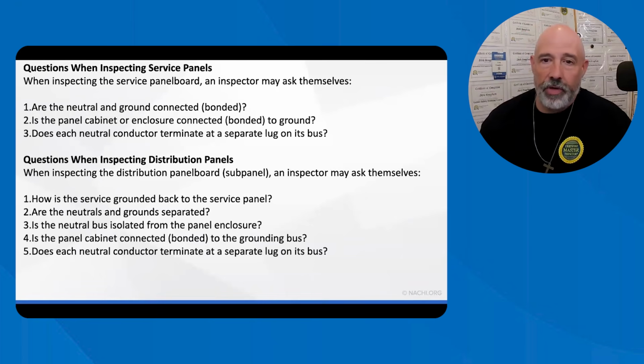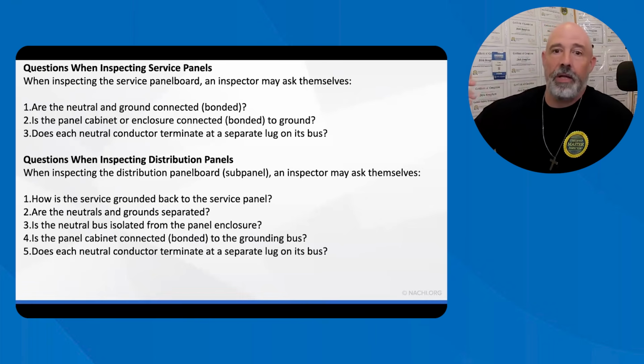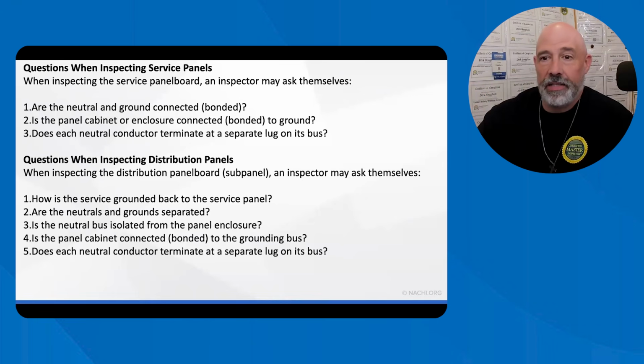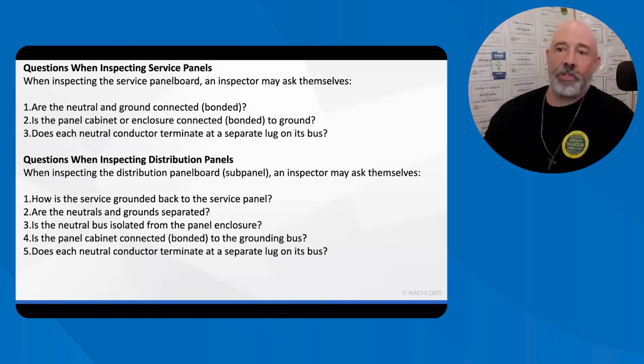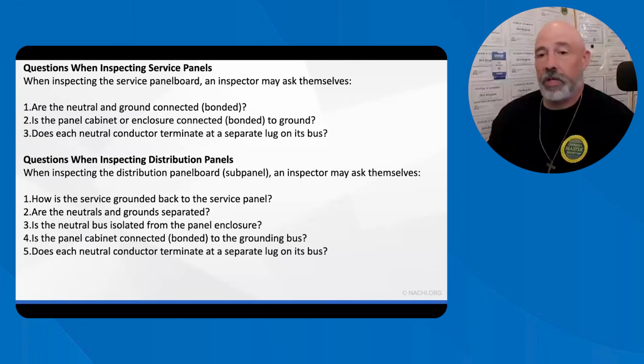Just remember that. It's an important note: every structure is required to have a grounding electrode system. If there are any present in the structure, they must be bonded together. If a detached structure has a remote distribution panel located at the structure, then it's required to have a grounding electrode system of its own. So there should be another grounding wire at a different area. It's also important to understand that if the detached structure is being fed by a single branch circuit, it contains an equipment grounding conductor that is used for grounding the non-current-carrying metal parts of the equipment. So further evaluation, always further evaluation if you have to.